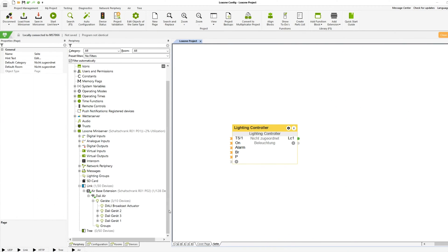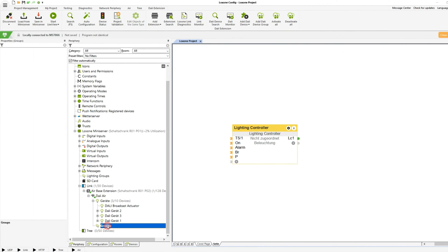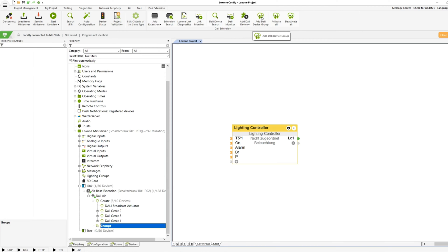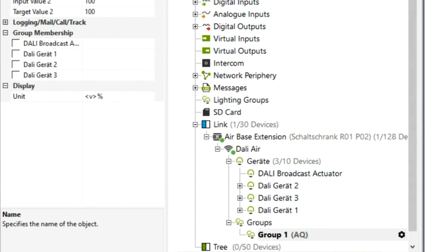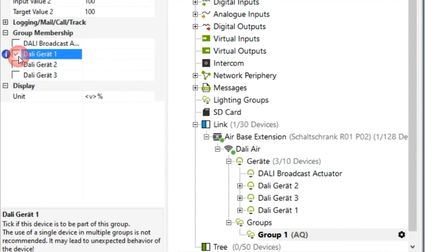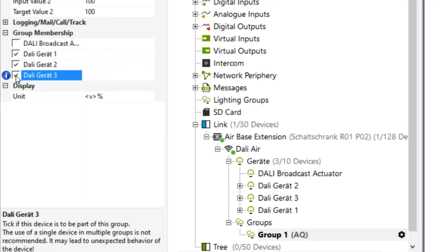If several DALI lights are to be controlled simultaneously, a DALI group is recommended. This has the advantage that the programming becomes clearer and there is no time delay when dimming the lights. When teaching the DALI devices, existing group assignments are loaded and created in Loxone config. To create a new group, the individual DALI devices must already be taught in. In the properties of a group, the desired taught-in devices can be selected and assigned to the group. Afterwards, the group actuator can be used in programming.